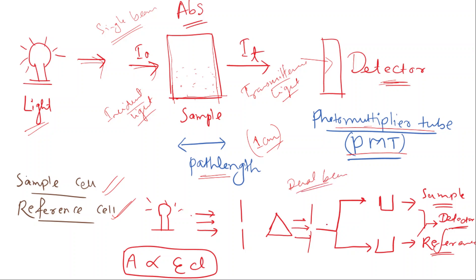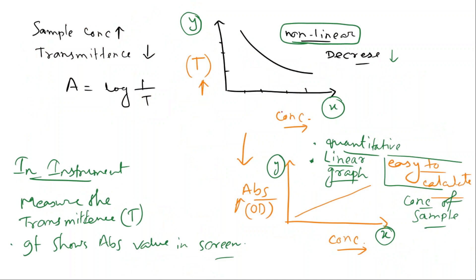There is also the dual beam configuration, where the light is split. One beam passes through the sample cuvette and the other through a reference cuvette containing distilled water. This gives a corrected, accurate reading of how much absorbance the sample produces.